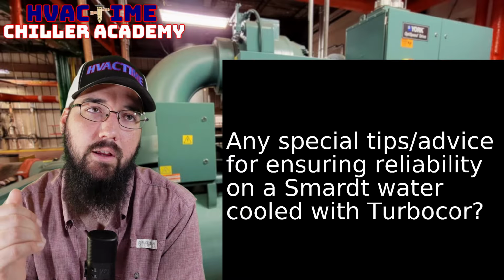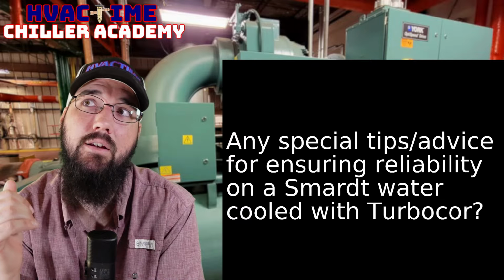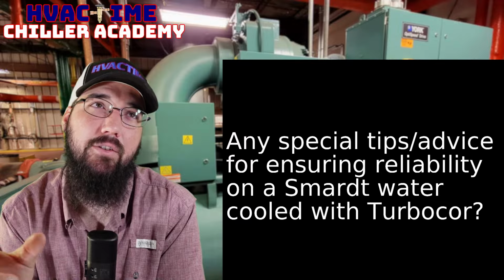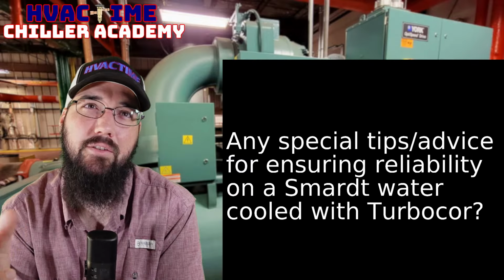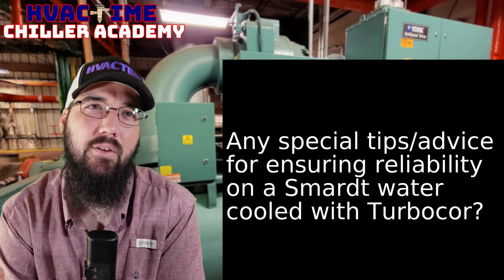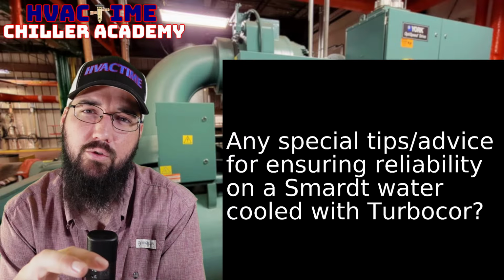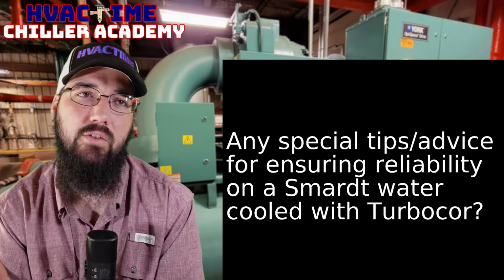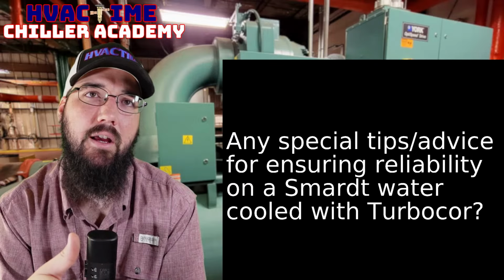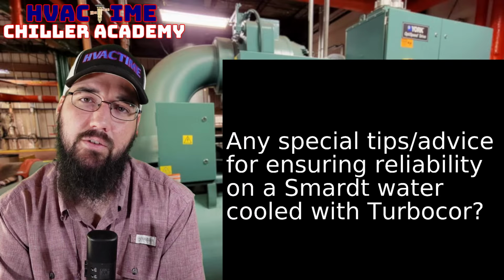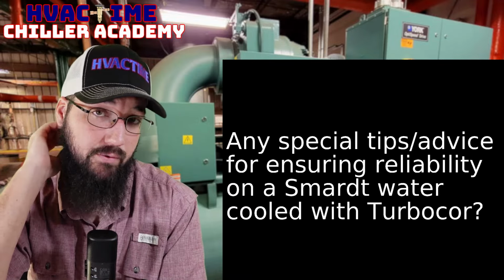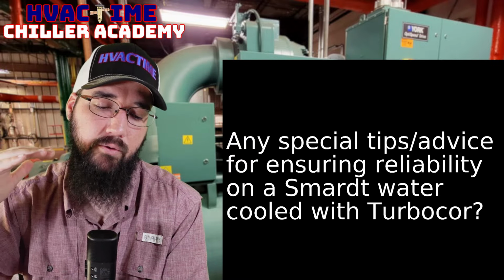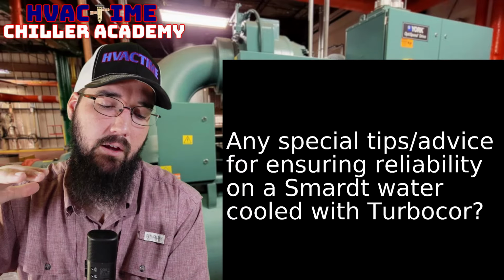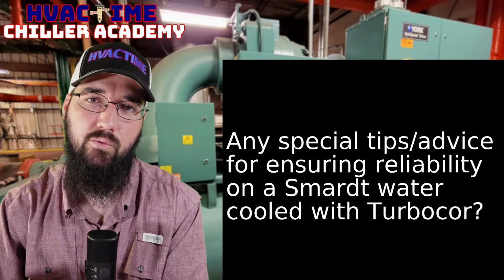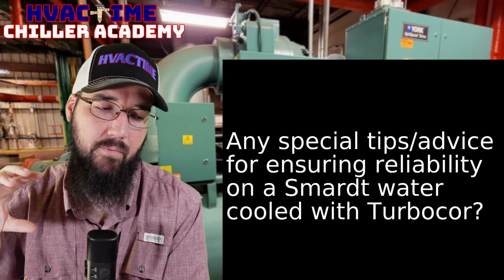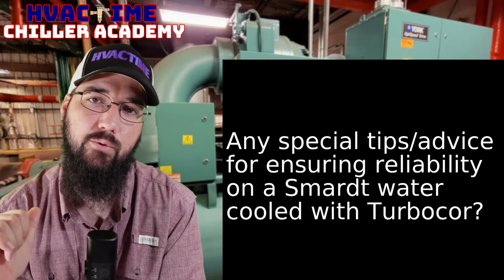These Turbocor cores, what they need, I think of this in terms of saturation. There is an actual pressure ratio that we need. Is it like 1.6 or something? I think it was like a 1.5 to 1.6 minimum ratio in order to move liquid refrigerant. But ultimately, I think of it in saturation. So what I found was I had to get my saturation about 10 to 15 degrees of separation, or even my water temperatures for that matter. Until my evaporator or chilled water temperature was about 10 to 12 degrees below my condenser water temperature, I would have trouble getting the liquid refrigerant to feed into the compressor for cooling.